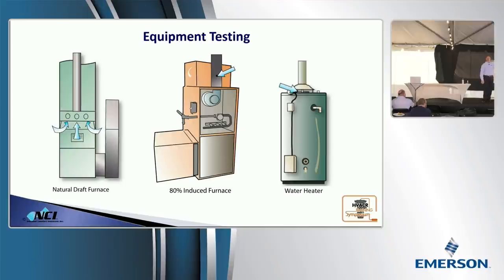So we want to test before any dilution air has mixed outside the combustion process. So anything after that draft hood is a diluted reading, and you're going to get really screwy numbers. At a minimum, there's typically 100-to-1 dilution rate there. So stay away from measuring above the draft hood for your combustion readings. Measure at the outlet of each heat exchanger opening. Well, when we get into 80% furnace, there's no draft hood. Now, you do want to be a minimum of 12 inches away from the inducer outlet. So you're going to need to install a test port in the flue.